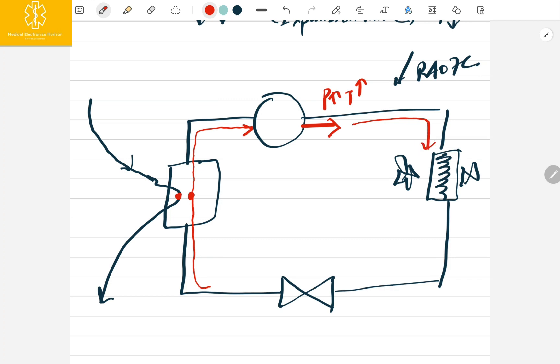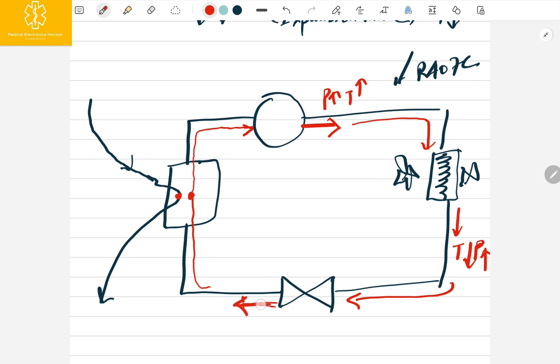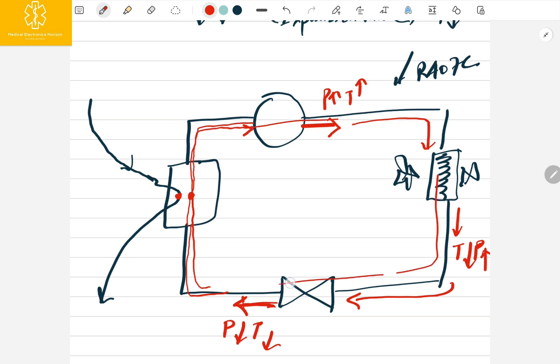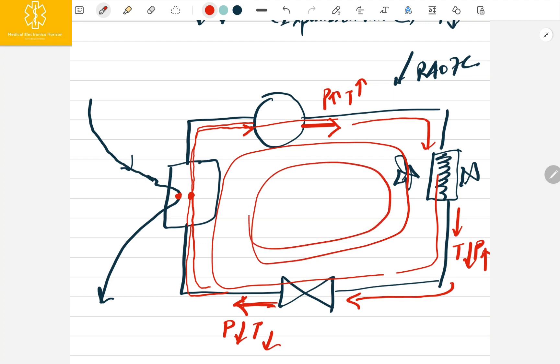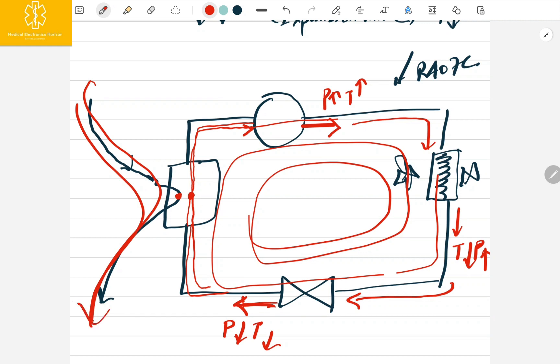When this gas enters the condenser, the fans make the gas cold. The gas comes out with lower temperature and high pressure. When this gas enters the expansion valve, it comes out with lower pressure and lower temperature. This lower temperature and lower pressure gas then enters the PHE, chills the water, and enters the compressor again. This cycle repeats continuously, giving us a continuous cold water supply for our MRI system.